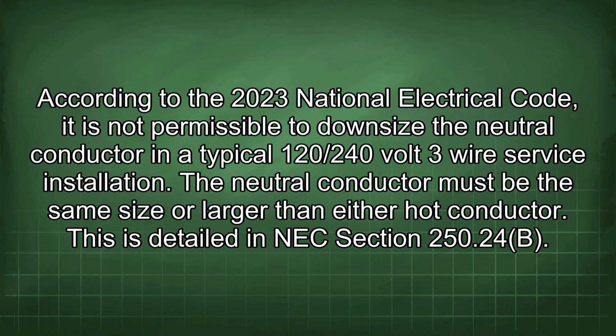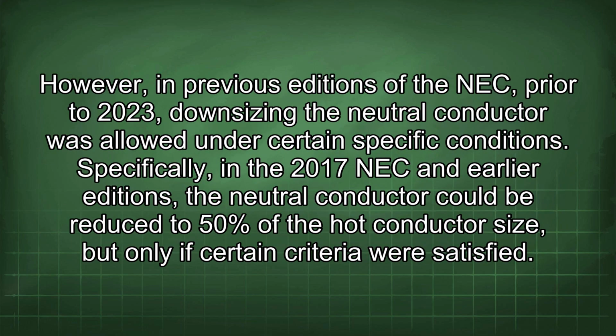According to the 2023 National Electrical Code, it is not permissible to downsize the neutral conductor in a typical 120/240 volt 3-wire service installation. The neutral conductor must be the same size or larger than either hot conductor. This is detailed in NEC section 250.24(B).